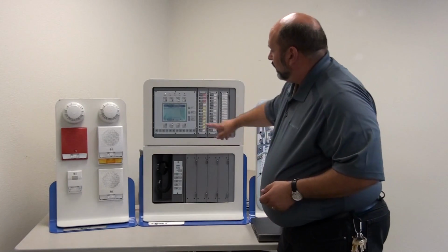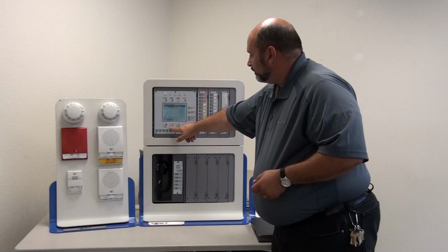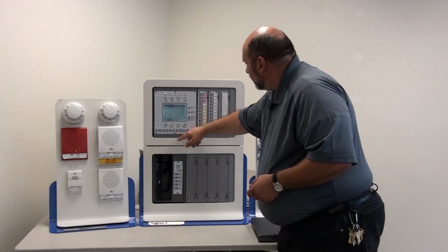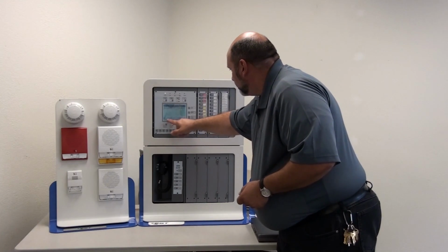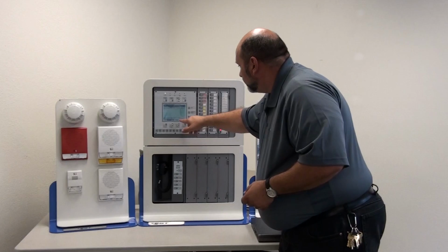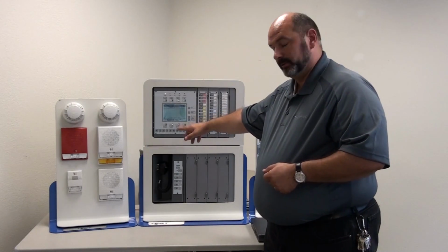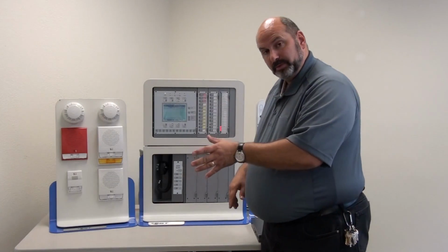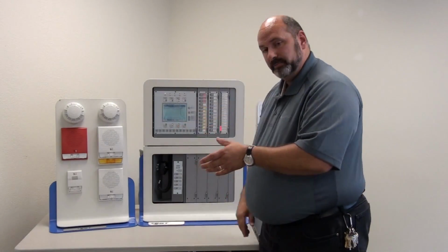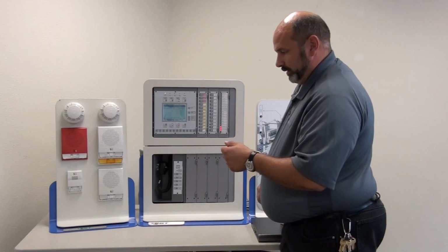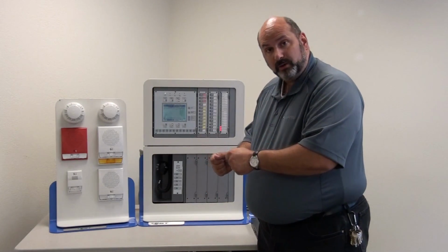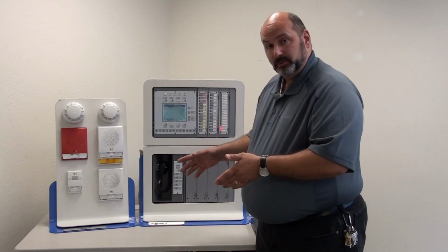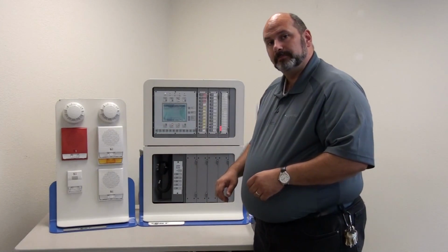Okay. Now, right now I have a supervisory that's lit. I can press the little check mark on the panel and it will tell me that the supply store fire sprinkler tamper switch is activated. Okay. And that's something that you can go and you can look at the riser, the sprinkler riser that is indicated on the fire panel, and check to see that somebody hasn't shut the water off to your building, or maybe that a piece of equipment or something was run into the tamper switch.